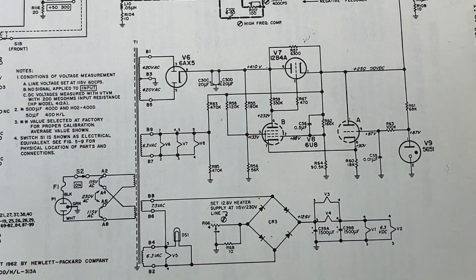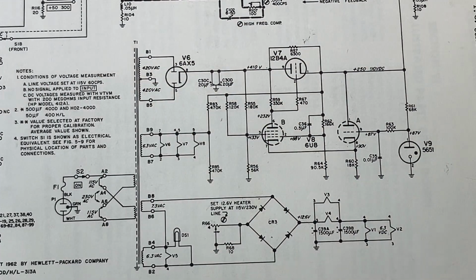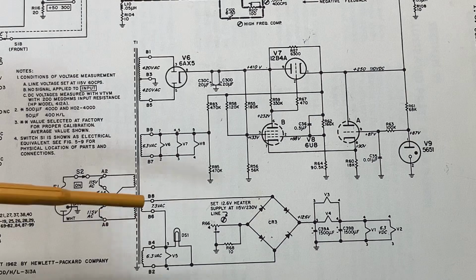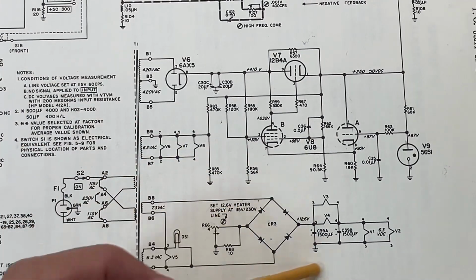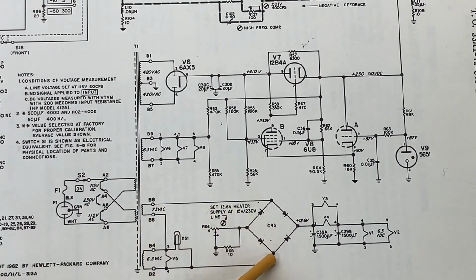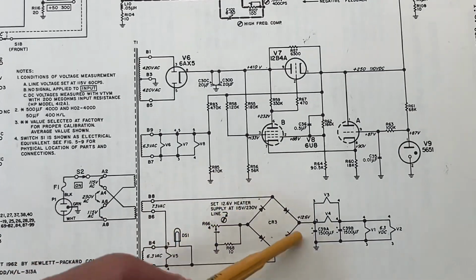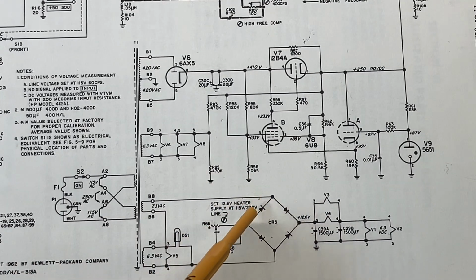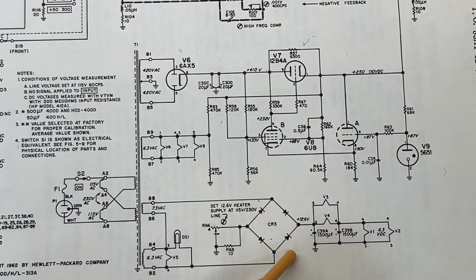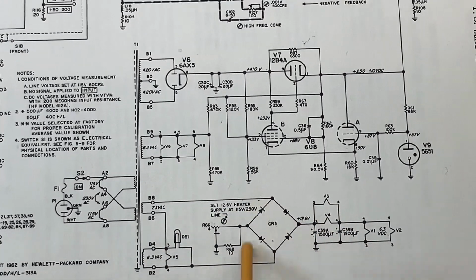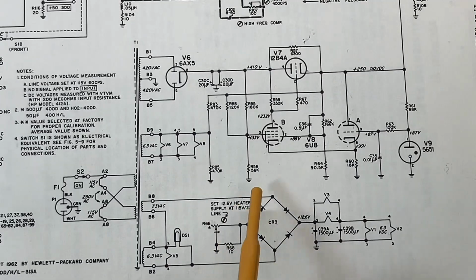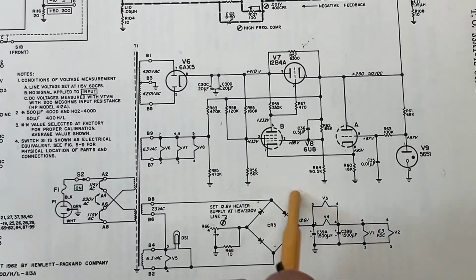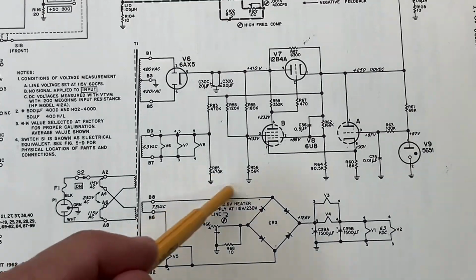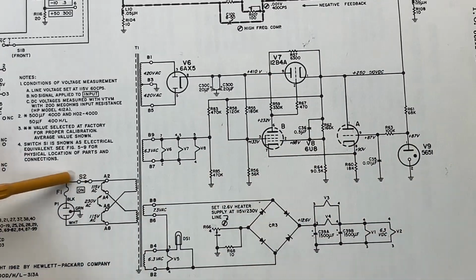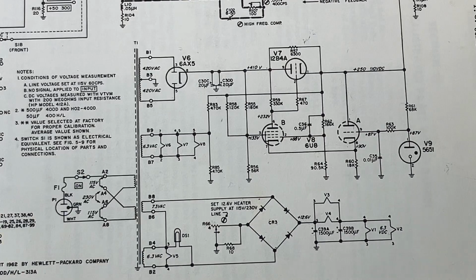So here we are zoomed in on the power supply section of the schematic of this instrument. I had a feeling that maybe the silicon rectifier here was shorted or something like that, because they had already replaced the selenium rectifier that usually goes here with a silicon bridge rectifier. And so I checked these diodes out and they are not shorted. There's no way for me to measure the voltage because it blows the fuse immediately upon power up.